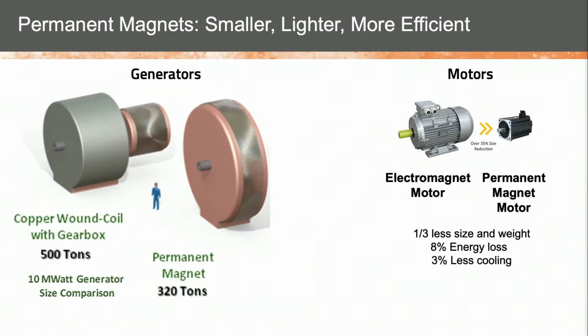That means we can make smaller, lighter, and more efficient generators and motors. That 10 megawatt generator is now only 320 tons when we use permanent magnets. Also, for motors, a permanent magnet motor is about 1/3 less size and weight than an electromagnet motor. And because it doesn't contain coils of wire to produce the magnetic field, there are less energy losses, so it's more efficient, meaning it also uses less cooling.